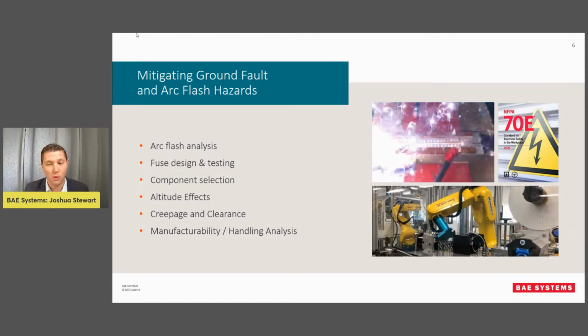Understanding altitude effects: the voltage breakdown of air actually decreases as altitude increases. So insulation and clearance and creepage allowances that are acceptable at 0 feet of elevation may not be enough at higher altitudes.